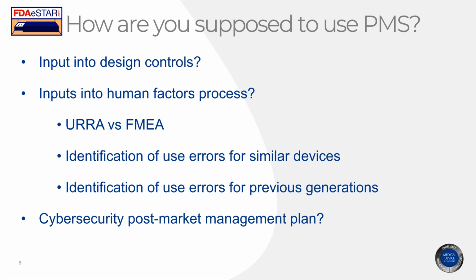You should make sure you include those use errors in your URRA, and you should consider risk controls for those use errors, and if possible, design it out of your device. So you should be doing these activities not at the very end, just before you submit, but very early in your design process when you're still working with prototype concepts and some early proof of concept designs, maybe 3D printed models. That's when you want to be looking at the use errors that occur for other devices and try to figure out ways to eliminate those by design, which is what the first priority is for risk controls, always in 14971. Eliminate it by design or method of manufacture first.